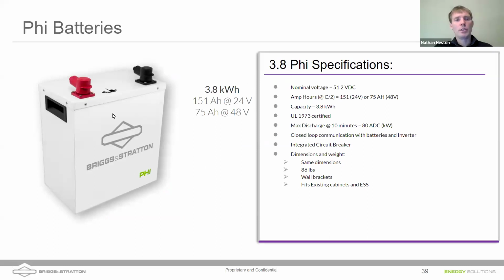We have the PHI battery, comes in 3.8 kilowatt hours -- I believe 3.86 kilowatt hour sizes, in either 24 volt or 48 volt. The 24 volt version has 8 cell stacks in series, the 48 volt has 16 cell stacks in series, both containing the same amount of overall energy, but one delivering more current for a longer period of time, the other delivering less current but at a higher voltage, double the voltage. So the same overall energy.